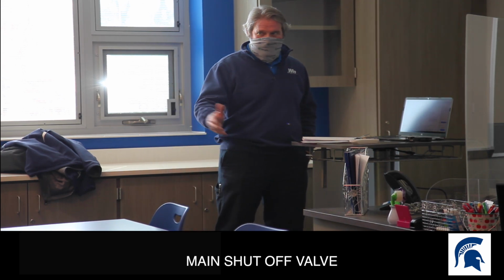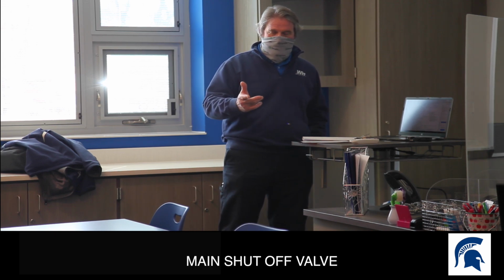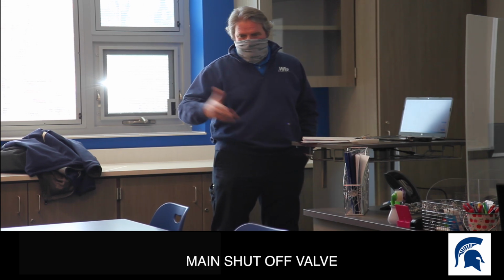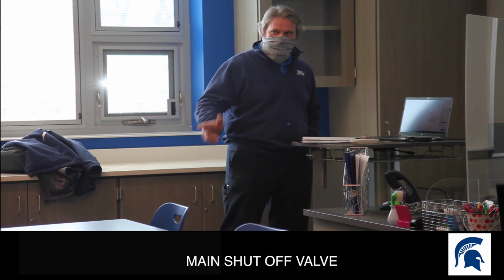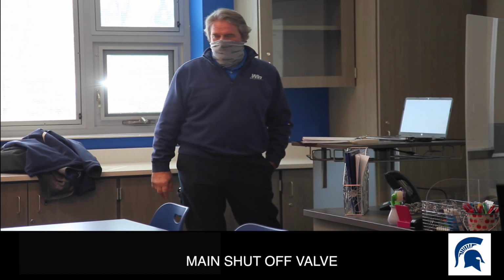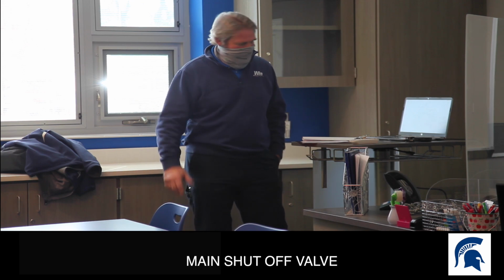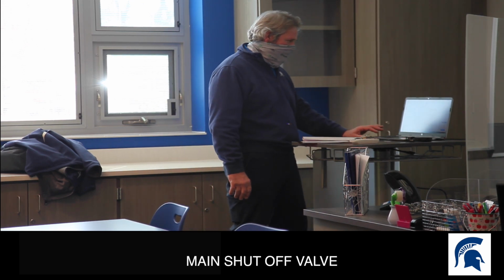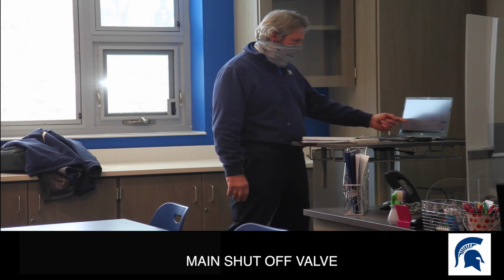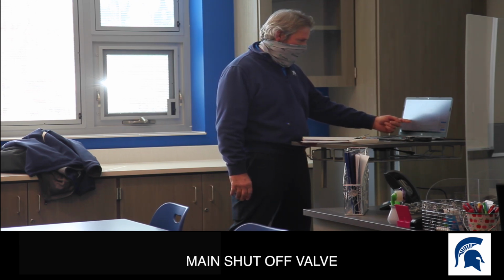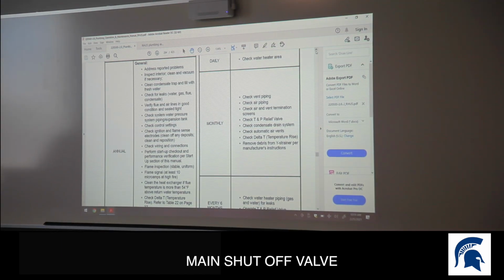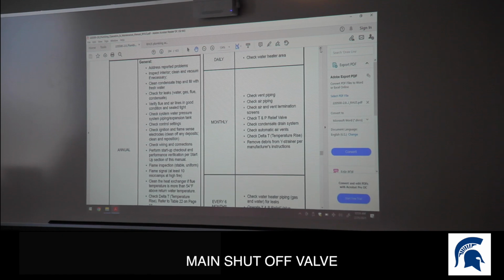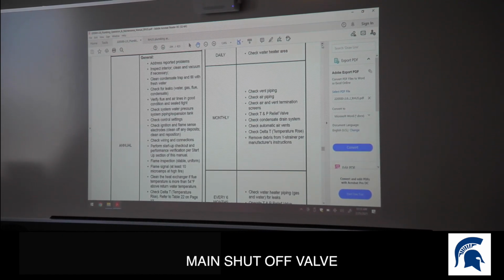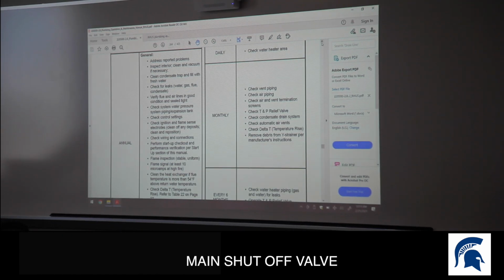And keep it clean, nothing around it. That's a big thing they'll talk about as well in here. You know, no mops and buckets and paint cans. Nothing is supposed to be in a boiler room except installed equipment. So yeah, there you go, right. That'll help you a lot with that. Then they're asking you to perform a start and checkup to verify that's a whole deal that you have to do when you do it for the state. You're supposed to perform all these duties to make sure that the boiler's in good shape.